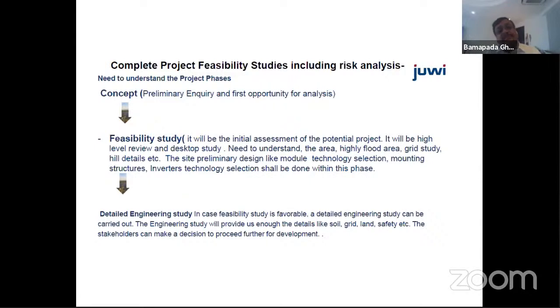So this part is more important, the feasibility study and then the detailed engineering study. The detailed engineering study provides the entire concept and design inputs, like the civil perspective, soil frictional values, grid studies like grid values and fault level, everything comes through grid studies. Then from a safety point of view you need to check if lightning issues exist, check the plant contour, and based on the contour check the technology again. So a lot of things like AC/DC ratios and wind factor all come up after the detailed engineering studies.